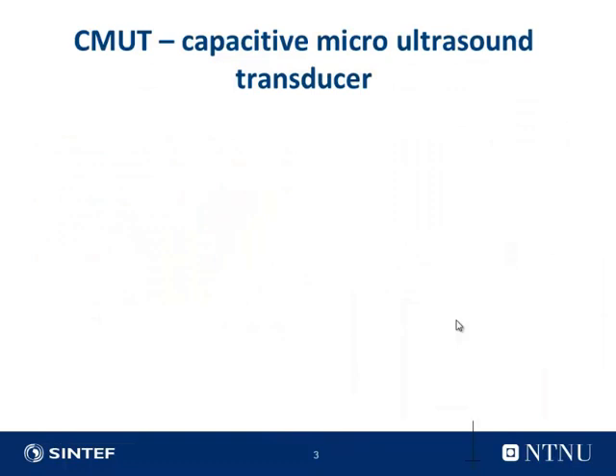So I'll just go briefly through what a CMUT actually is. The conventional ultrasound probes are linear arrays of bulk PZTs, slabs of PZT and matching material. Because of limitations in the processing capabilities, it's challenging to produce probes with a high frequency to get the resolution we need here. Also, they are linear arrays, so you cannot make a 2D structure in a typical way, and that means you can't do 3D imaging and beam steering, where you want to put a phase delay on one side or the other to control the beam.